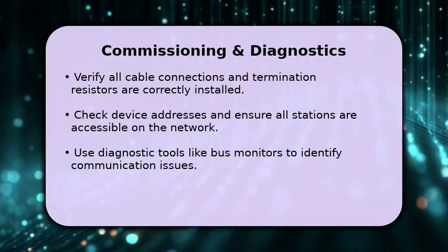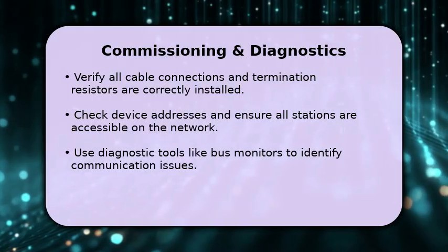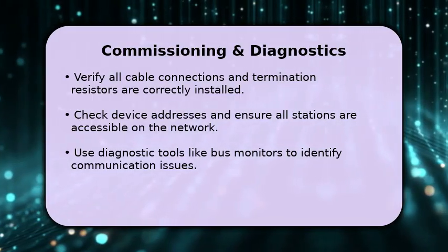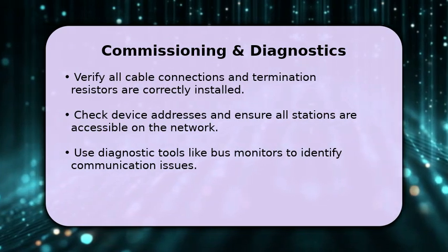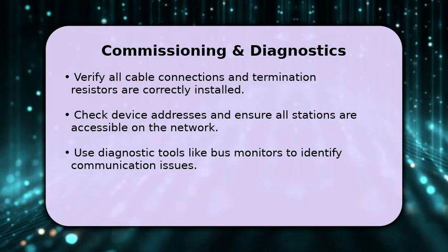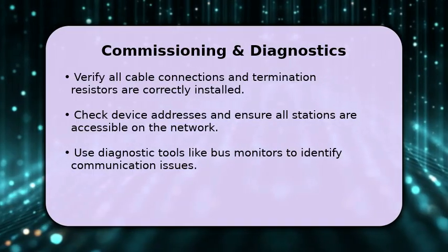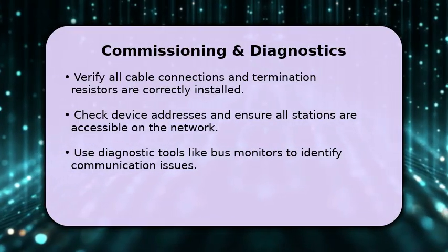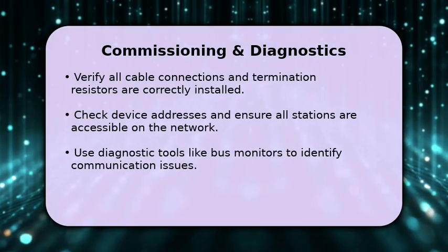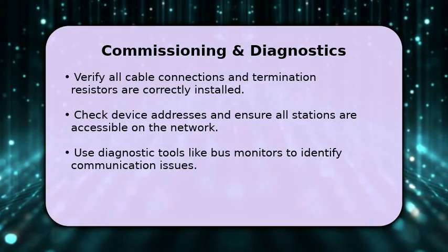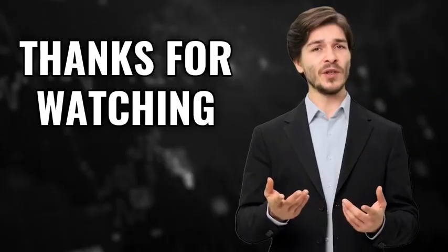Utilize specialized diagnostic tools, such as a Profibus bus monitor, to check signal quality and identify any communication errors. Pay attention to diagnostic messages from devices, often signaled by a red LED, which can pinpoint specific faults for quick resolution.